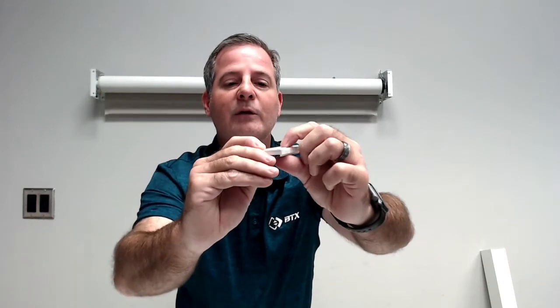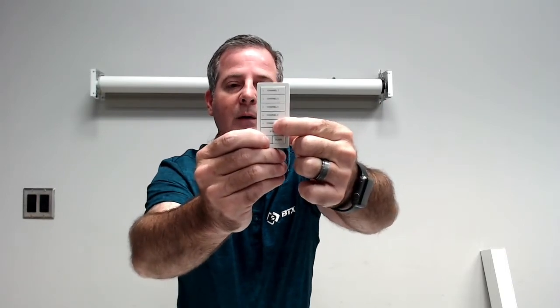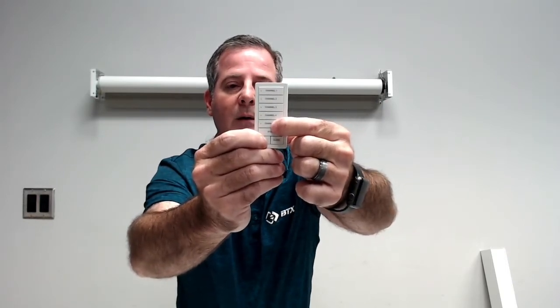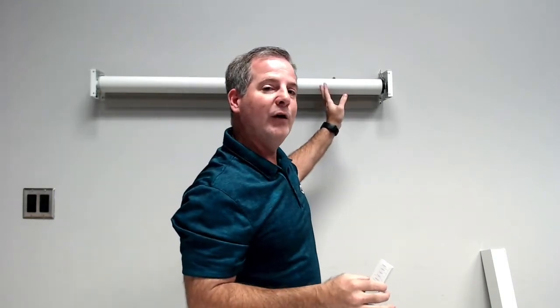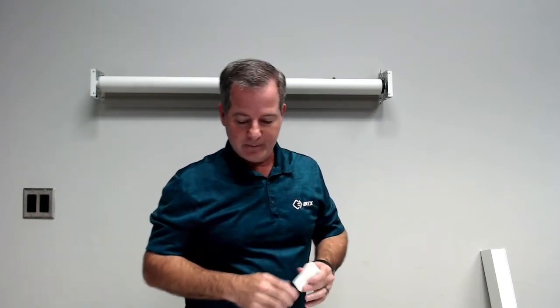Got to make sure you get the slow flash on this. Stop and open. It jogs, and now if I light up number five and try to run it, it will not run that particular unit. It stays in this mode, this pairing mode, for about two minutes. The motor will jog eventually, and it'll go out of pairing mode.